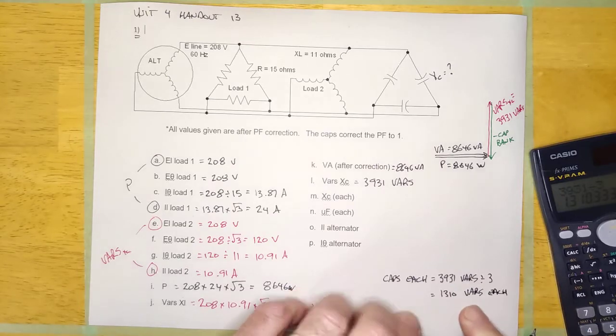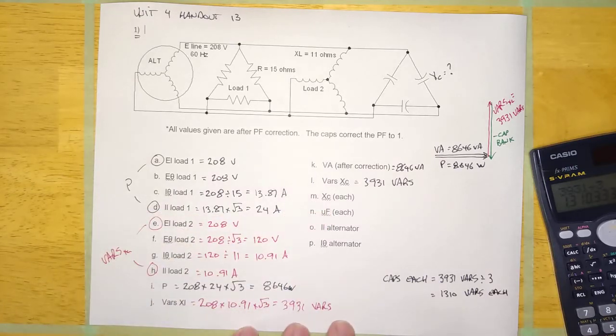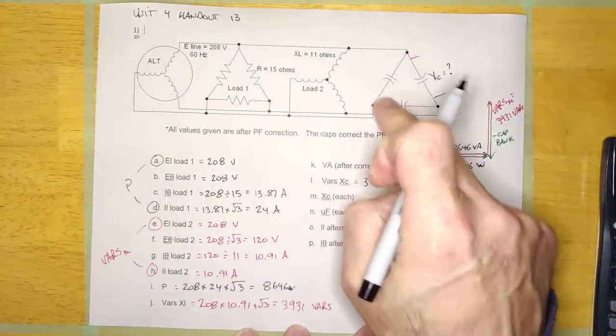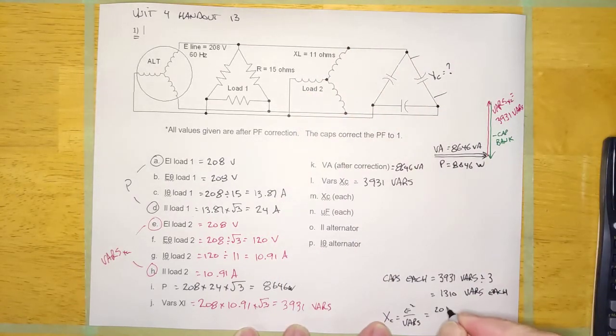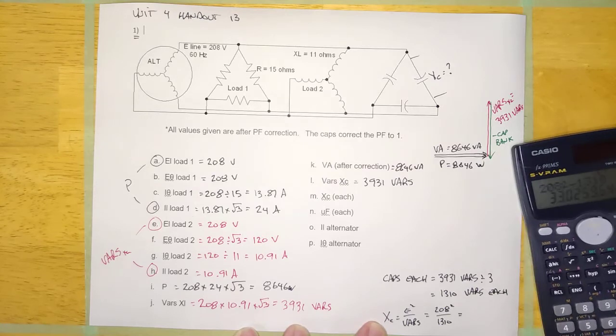The next thing is to figure out how many ohms they are each. XC equals E squared over vars. The voltage dropping across them is 208 since it's delta — if it were Y it would be 208 divided by root 3. So it's 208 squared over 1,310.